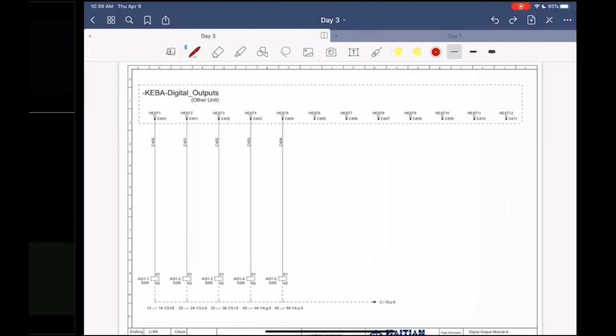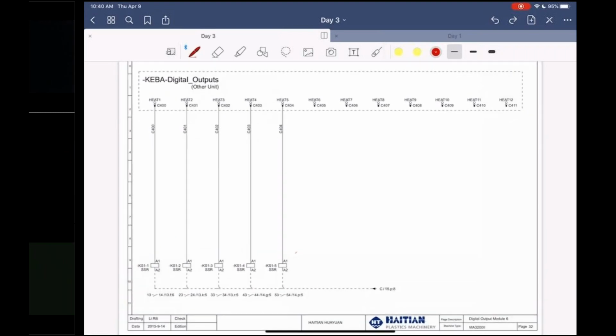All right, continue. Again, you have your SSRs for your heat band heater circuits, so you have your heat 1, 2, 3, 4, 5. Sometimes they do give you extra heater locations, and they do give you an extra SSR on most machines, not 100% of them. I usually do this on some startups: if a customer has, for example, a hot sprue, you can wire that into heater 6. You just use your inputs, go to the SSR, change the voltage to 220 volts, tap off the transformer or put a new transformer in there for 220 volts, and you can use heat 6 as your hot sprue. And it will be controlled with the controller because it also has the input from the analog input. You just connect that to the heater 6 input, and it'll read the temperature, and it should be good to go.